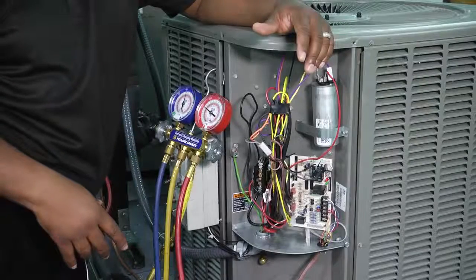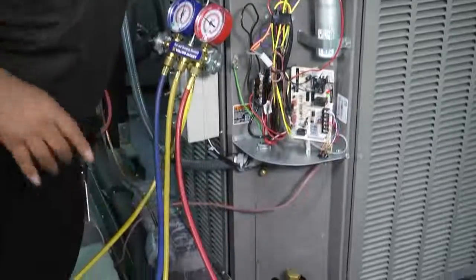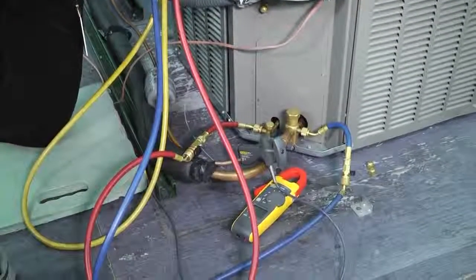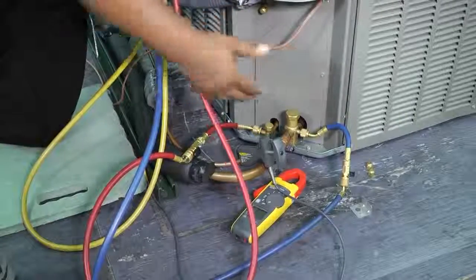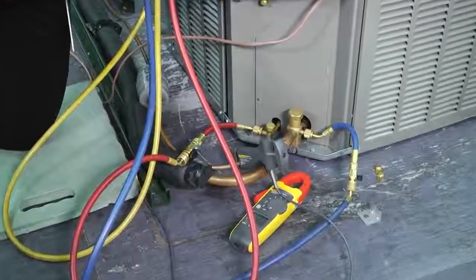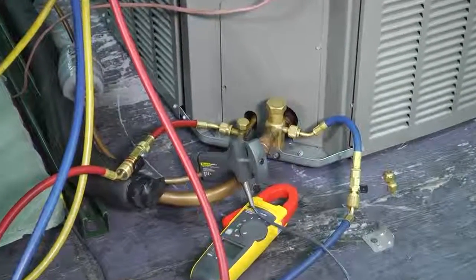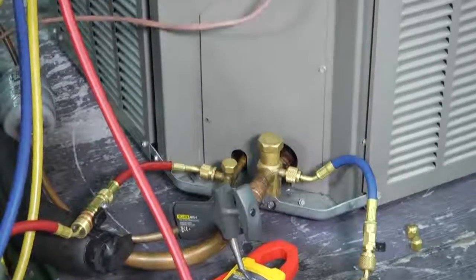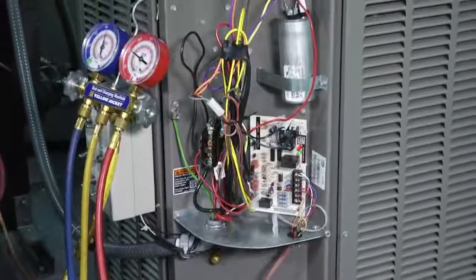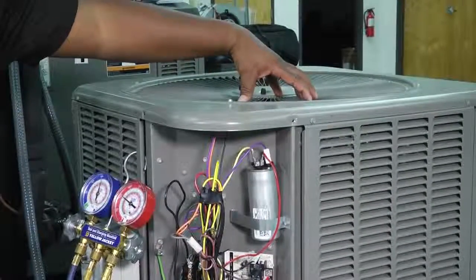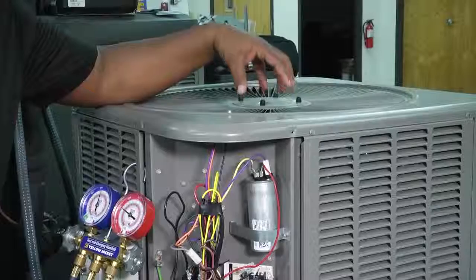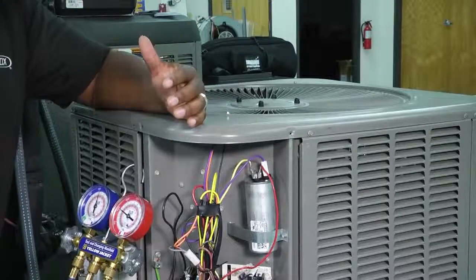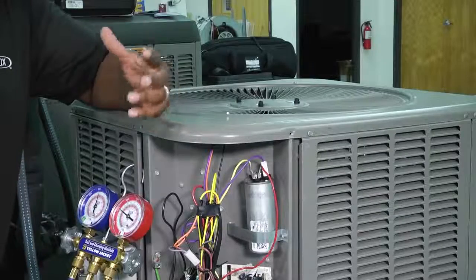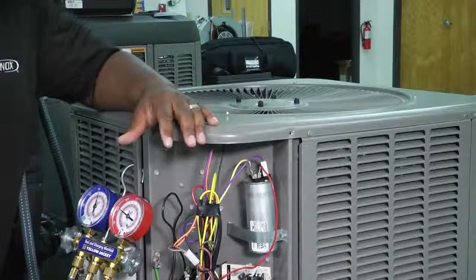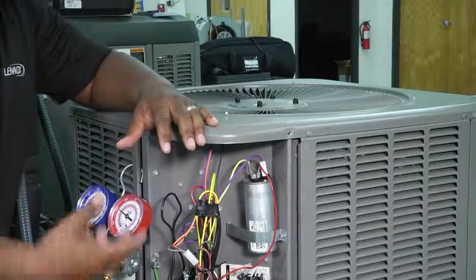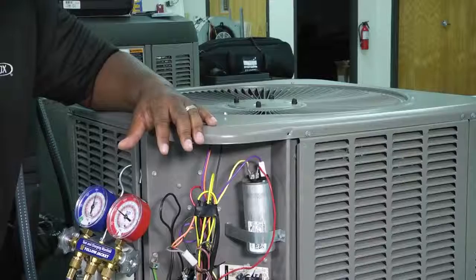One of the other things that we have to make sure of is visually we want to check our refrigerant lines and see if there's indications of oil. If we can see oil somewhere on our refrigerant lines or even on the wall plate there, a lot of times that can be an indicator just from sight that we may have a possible leak in our system. Now, when it comes to cleaning, another area that you want to check is actually to remove the top, or to look down and peer down inside and look at the interior, the inside of the condensing units. A lot of times leaves and different things like that and other types of debris, sticks, may fall into our unit, and we want to actually vacuum all of that stuff out, scoop all of that stuff out, and make sure the inside of the unit is cleaned as well.